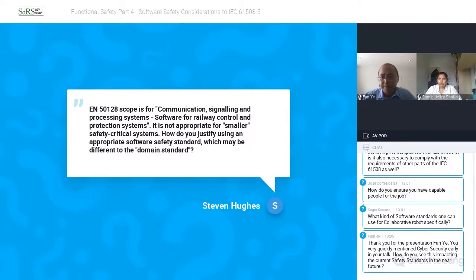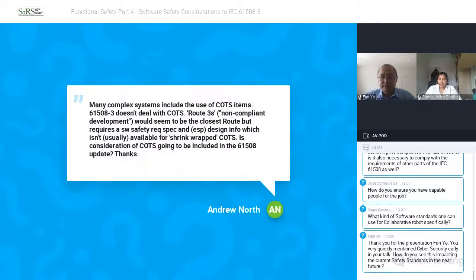Thank you. I think we've only got time for a couple more questions. The next question is from Andrew North. Many complex systems include the use of COTS items. 61508-3 doesn't deal with COTS. Route 3S, non-compliant development, would seem to be the closest route, but requires a software safety requirement spec and especially design info, which isn't usually available for shrink-wrapped COTS. Is consideration of COTS going to be included in the 61508 update?